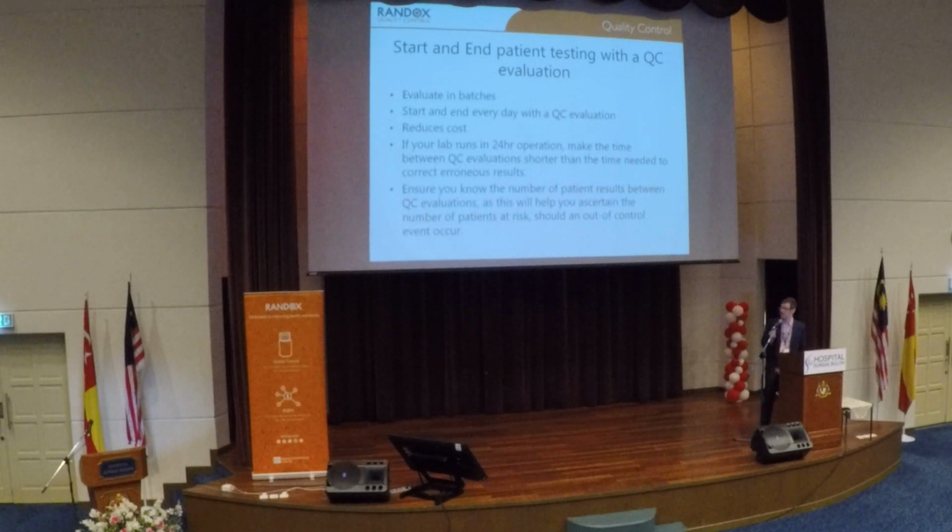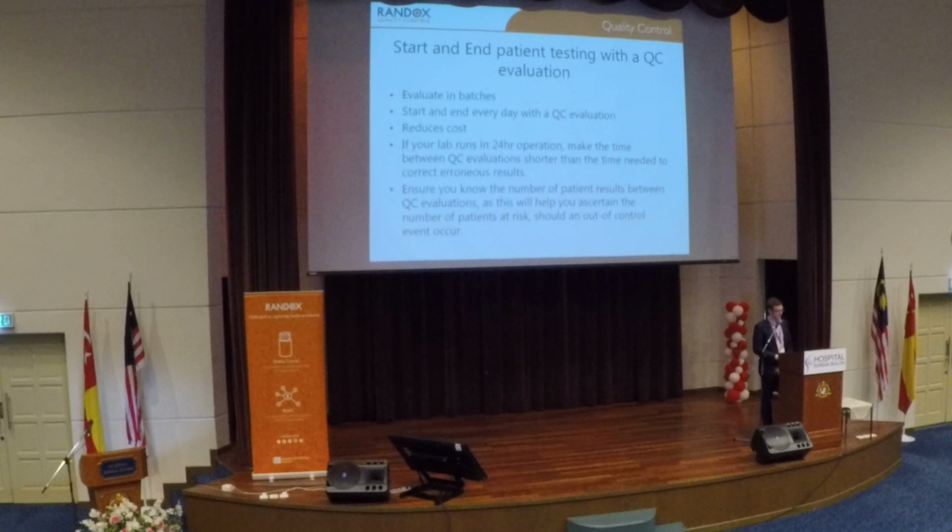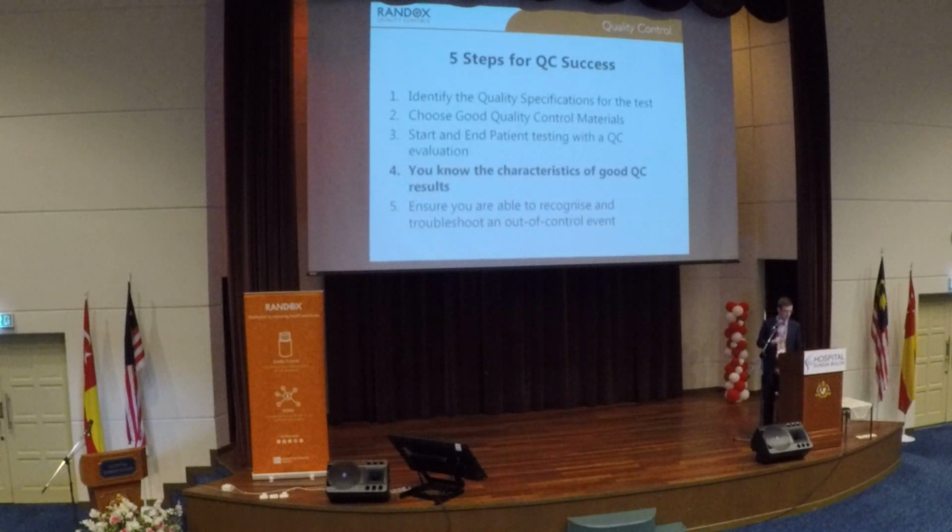So the idea here is to evaluate in batches. For this lab that was running 1,000 patient samples per day, it would maybe make sense for them to run QC after every 100 patient samples. That way, if they have an error, the maximum number of patient samples they will need to retest will be 100, which is still a lot, but it's nowhere near as much as rerunning 1,000 tests. So start and end every day with a QC evaluation as a minimum. It reduces your costs overall.